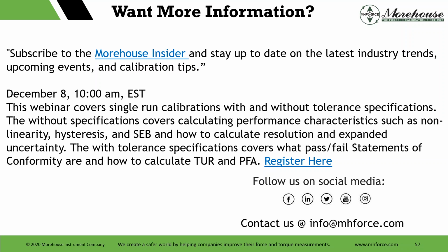Our next webinar is December 8th. And if you're watching this via video and it's past December 8th, 2020, you can just go to YouTube and find it. It covers single run calibrations with and without tolerance specifications. The without specifications covers calculating performance characteristics such as nonlinearity, hysteresis, and SEB, and how to calculate resolution and expanded uncertainty. We did a lot of that today. The with tolerance specification covers what pass-fail statements of conformity are and how to calculate TUR, test uncertainty ratio, and PFA, probability of false accept.